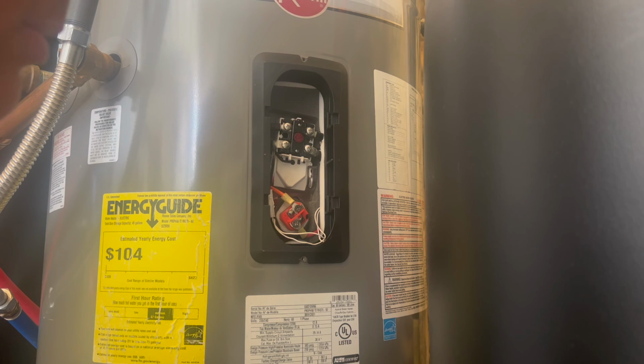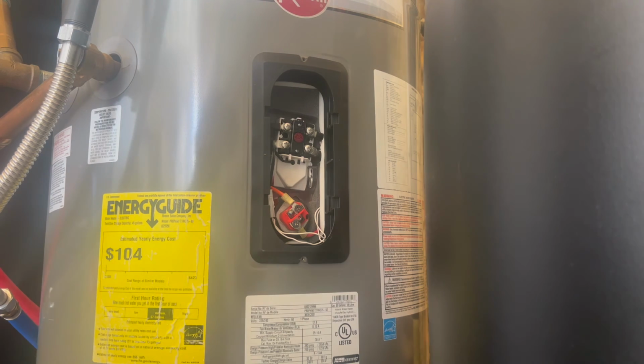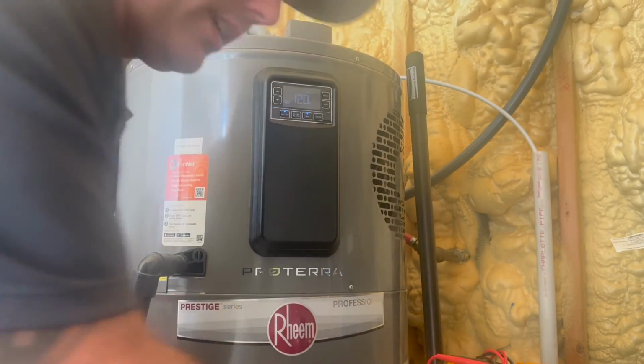But if it's giving you a temperature that doesn't make sense, got 65 degree air blowing out of the fan, and the heat exchanger temp is coming back at 85, well, we've got a problem. It's not reading correctly. Chances are if you took it out and put an ohm meter on it, it would not be within range. So you would be changing out thermistors. Okay, I'm gonna go ahead and put this back together.